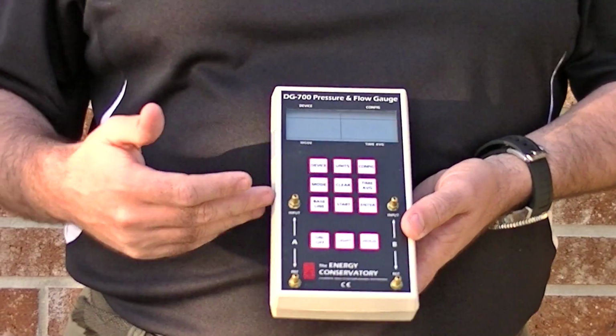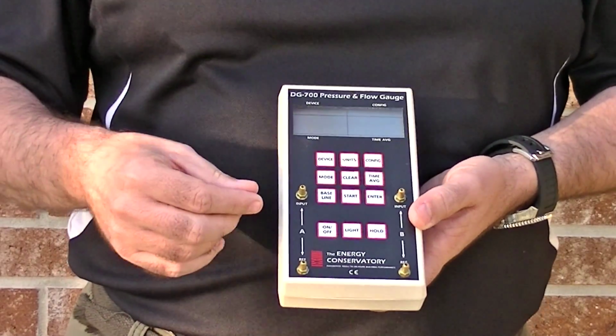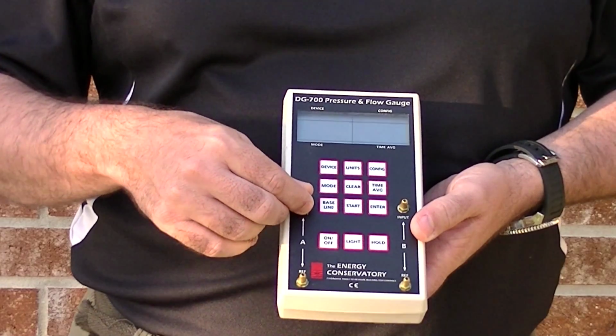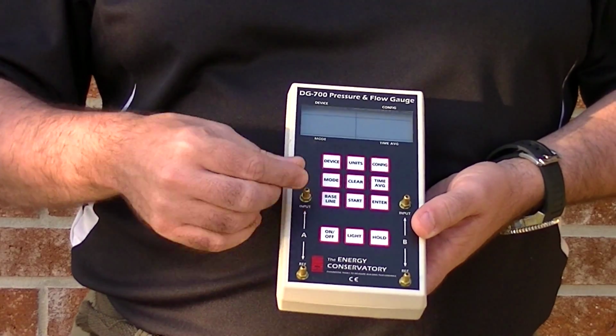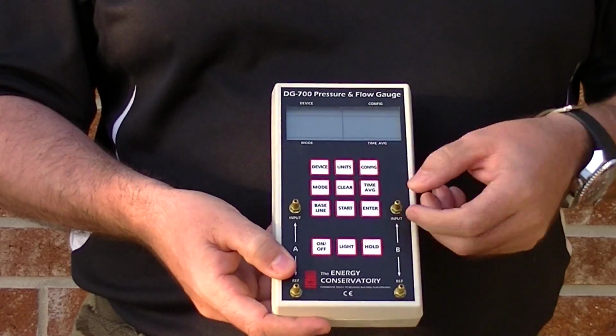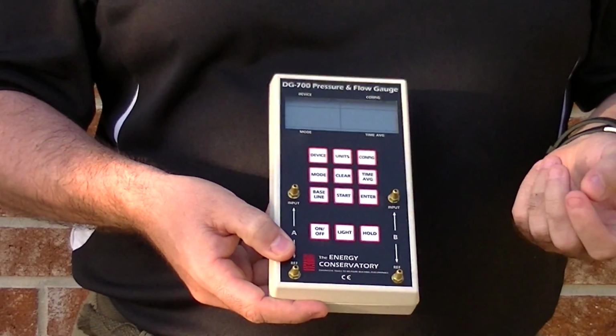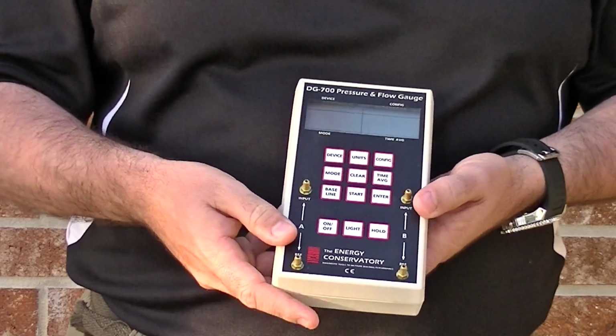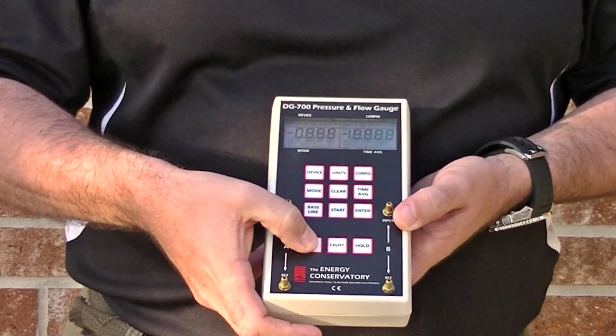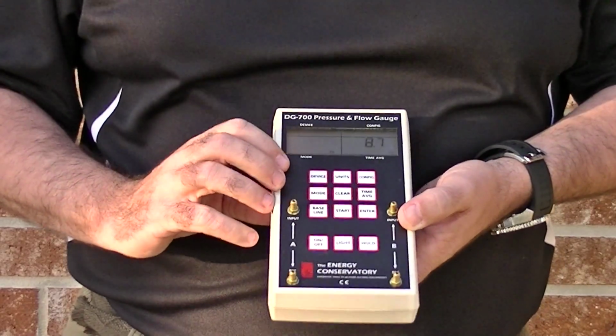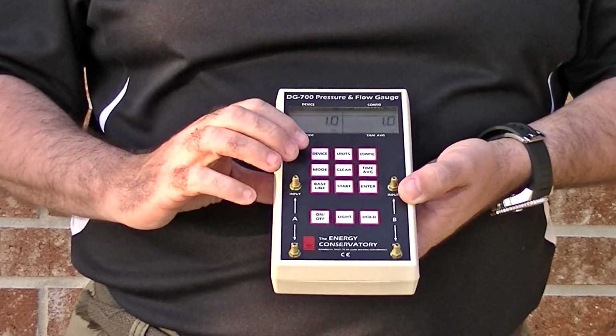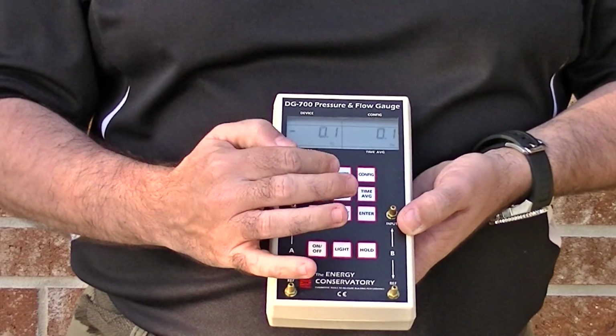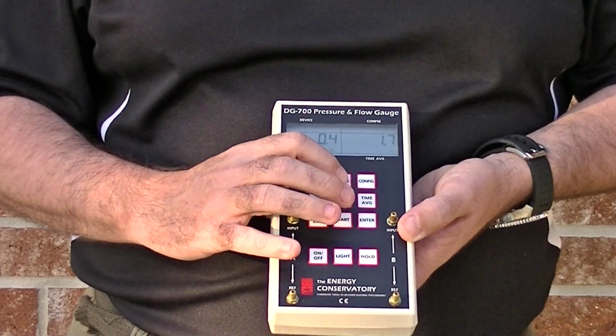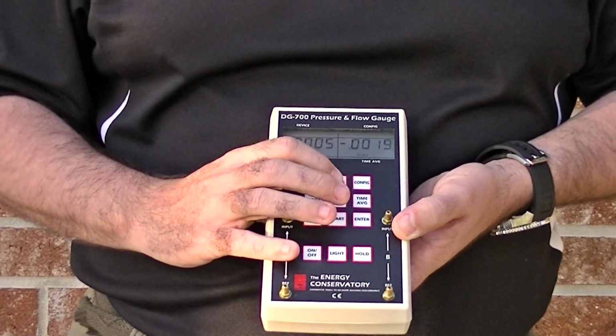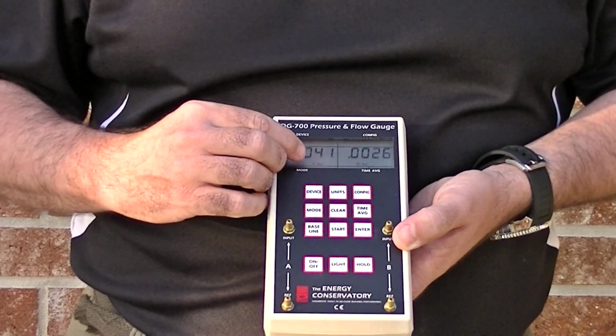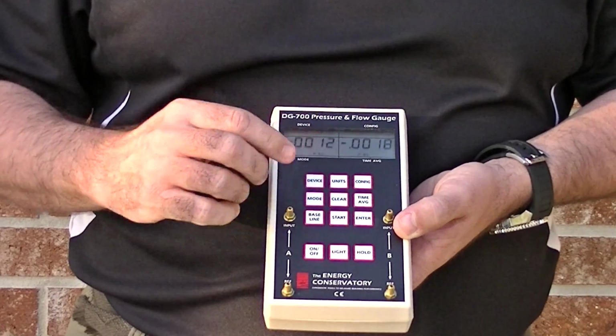So this is the DG700 gauge that I use. Now what we'll do is we'll connect one side to the static pressure probe that's on the return side of the air handler, and one side to the static pressure probe that's inserted into the supply side of the air handler. Basically, you turn the gauge on, keep it at reading pressure, and change the units with the unit button right here from pascals to inches of water column. Now it should display INWC, that's inches of water column.